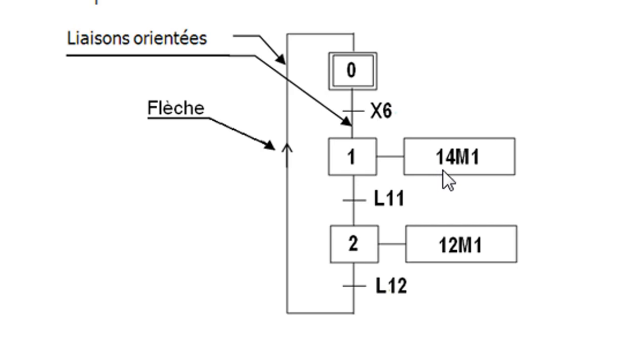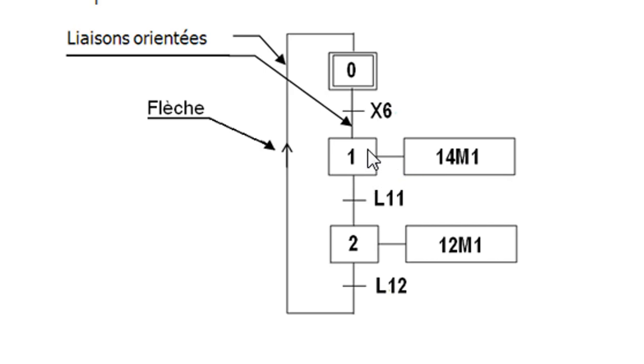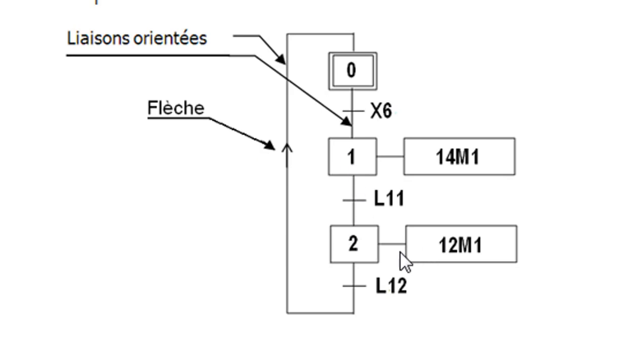When the transition X6 is verified and zero is active, we're gonna pass to the next step which is step one. Step one we're gonna do this action, activate 14M1. Then if it is active, we're gonna wait until L11 is true, then pass to the other step and see their action. And we continue like this then we come back again to start.